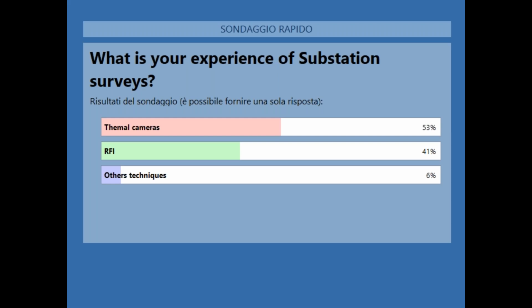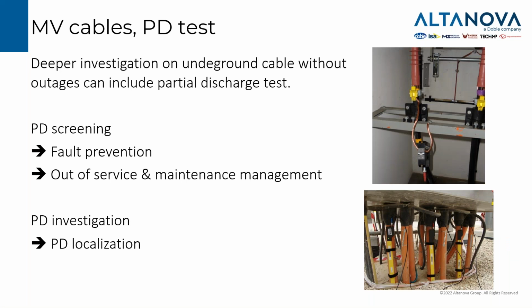So we move forward. Let me just close the window, move forward to our presentation, and we move to a higher level of investigation. So for both medium voltage and high voltage cable, we will discuss online partial discharge testing. The partial discharge assessment is a specific electrical test based on the signal emitted by defects in the insulation system normally. So we are talking about insulation problems.